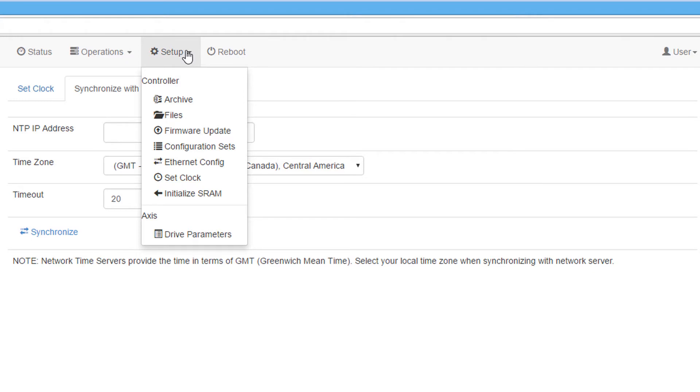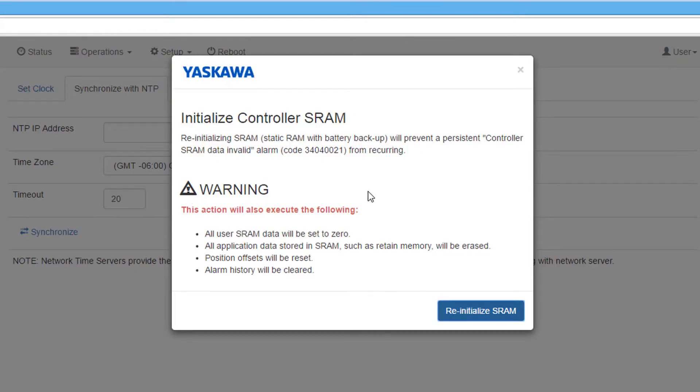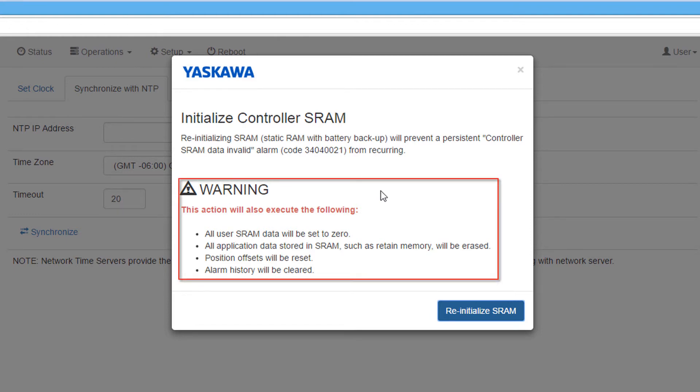The initialize SRAM function is not used often but is used when persistent SRAM data invalid alarms occur on the controller. This initialization clears all retained memory, position offsets, and alarm history.